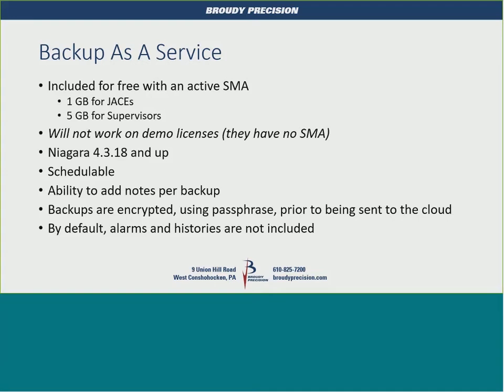Another thing that I don't mention here that I can show you is when you do a manual backup, there's a checkbox for, I think they call it retain or retention, and that will keep it on the server so that it doesn't get rolled off. So if you had like a starting point, when you left the job, this was the good backup, you hit retain, it won't get rolled off, but your automatic ones after it, once you hit the limit, will get rolled off.